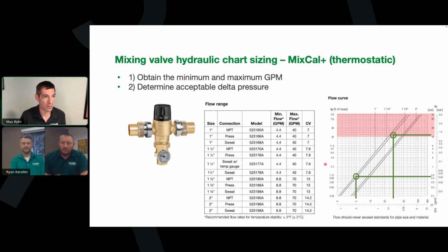But at the most extreme, if you went to the run out of this valve and you had a 25, 30, 50 psi drop across the mixing valve to save some money on the brass up front, you would have a lot of very weak showers in a hotel at that point, and we don't want that. So that's kind of where it would line up. In this case, you would have a 1.25 inch MixCal+.